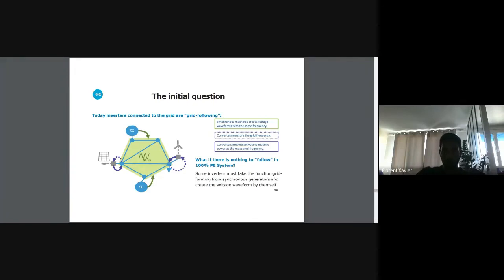Synchronous generators create the voltage and frequency of our system. So if we have more renewable energy, or no synchronous machines on our network, what happens? Renewable energy cannot measure what's happening on the network, so we need some renewable energy sources or inverters to take on the function of creating the voltage and frequency of our system. That's why we call it grid forming.